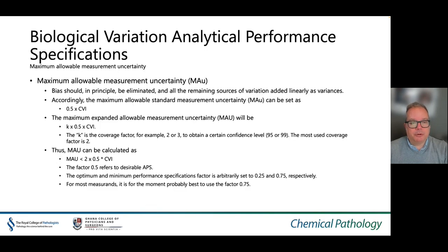Biological variation can also be used to set the maximum allowable measurement uncertainty. In this case, bias should in principle be eliminated and all remaining sources of variation added as variances. Accordingly, the maximum allowable standard measurement uncertainty can then be set as 0.5 times CVI. The maximum expanded allowable measurement uncertainty will be K multiplied by 0.5 multiplied by CVI, where K is the coverage factor — for example, 2 or 3 to obtain a confidence interval of 95% or 99%.